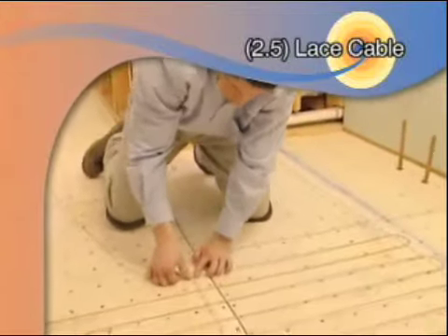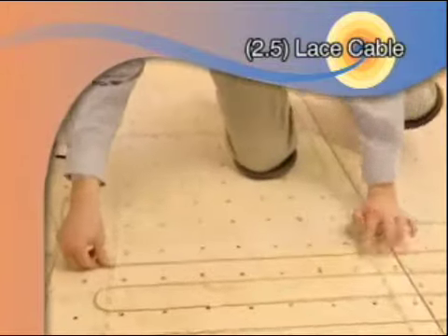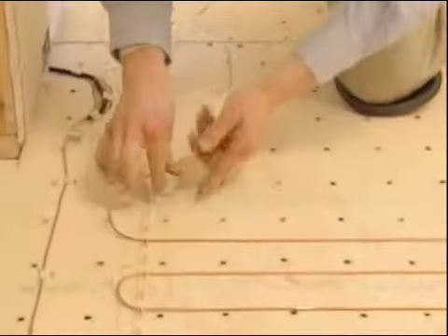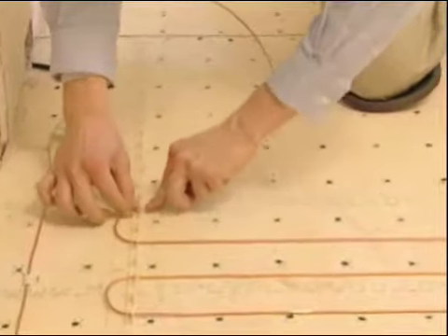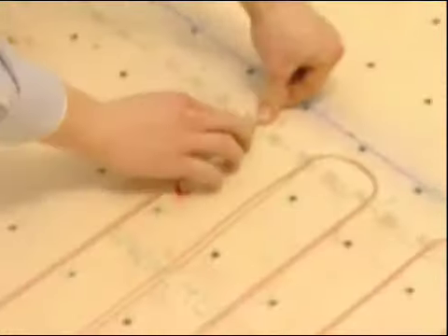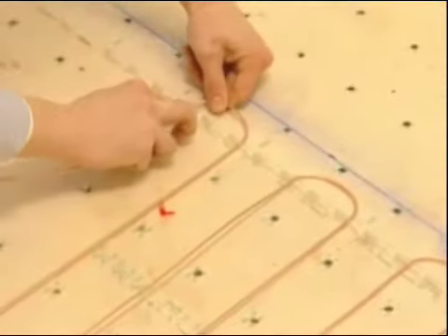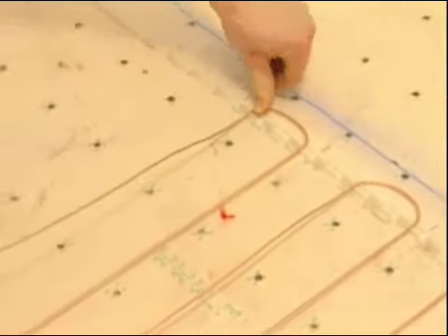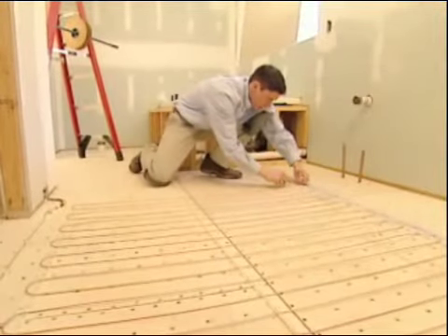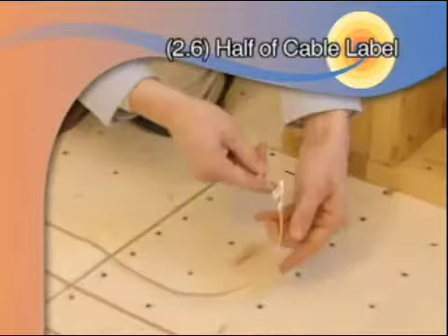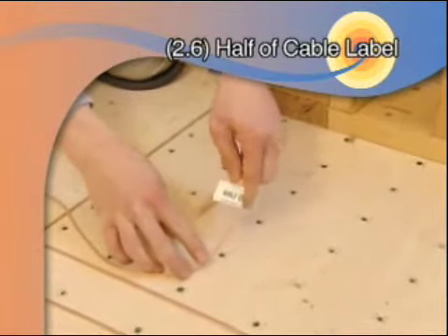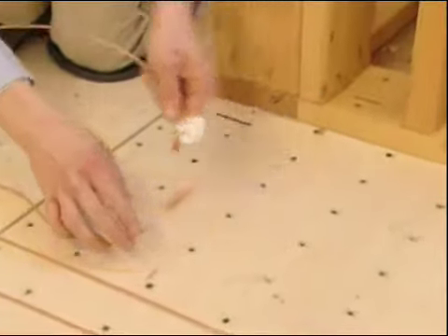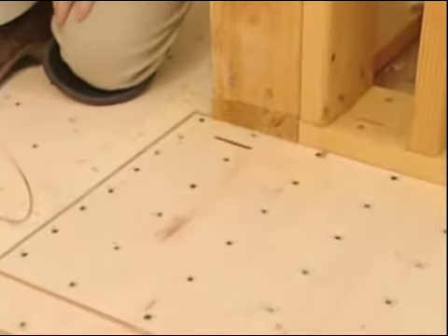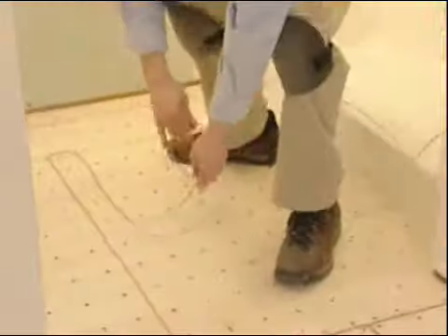Wind the cable at appropriate intervals and snap into the strapping slots. Then carefully turn the cable and snap into the next appropriate slot. Note: do not extend cable beyond the edge of the strapping. Continue laying out the cable until the 1/4 or half of cable length label is reached. Compare the location of the label to the corresponding 1/4 or half point previously marked on the floor.